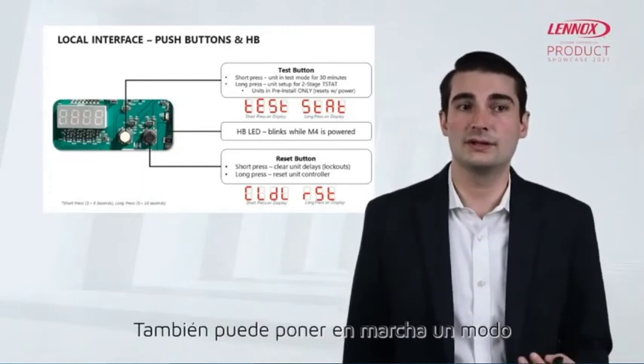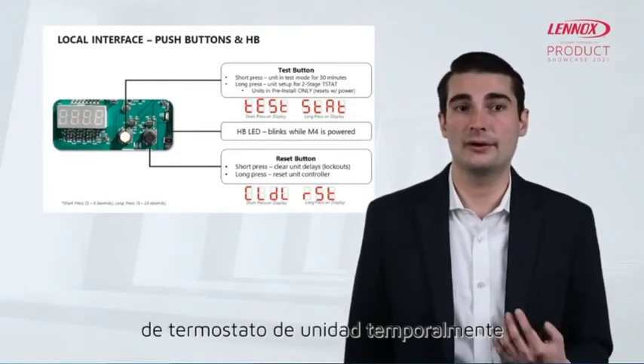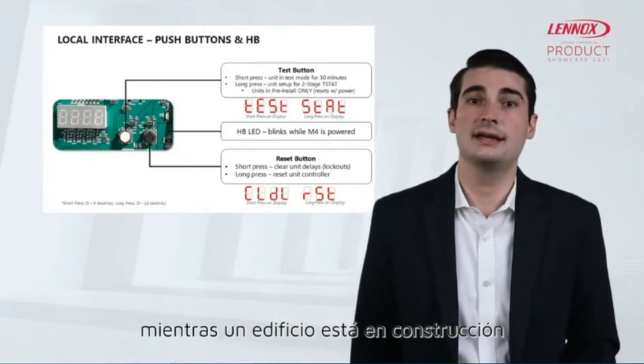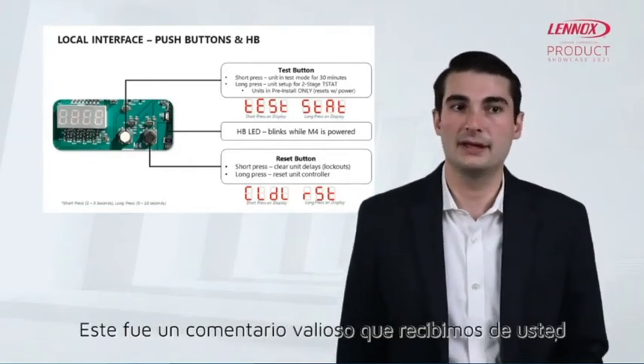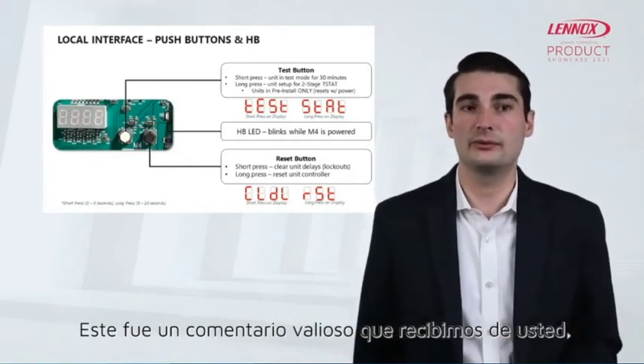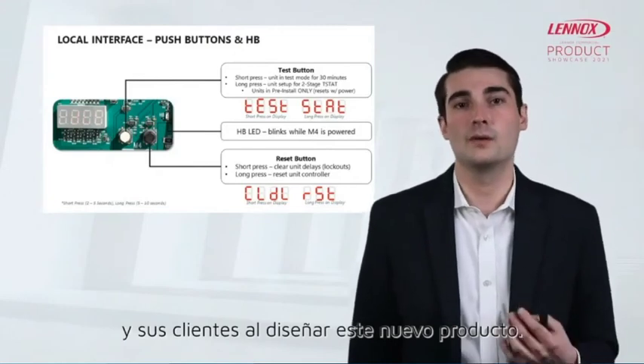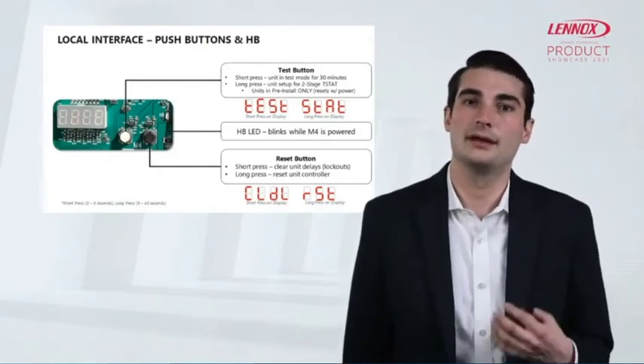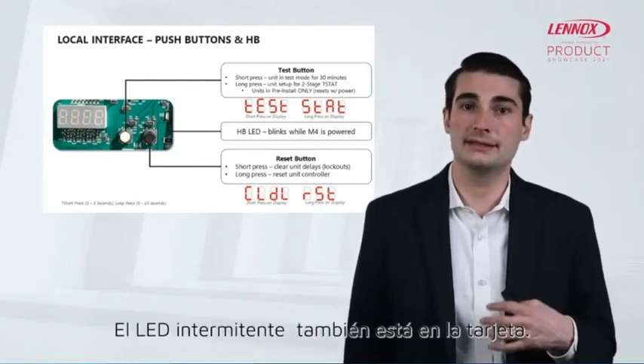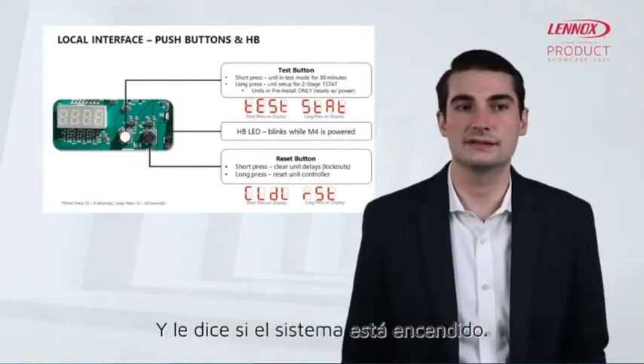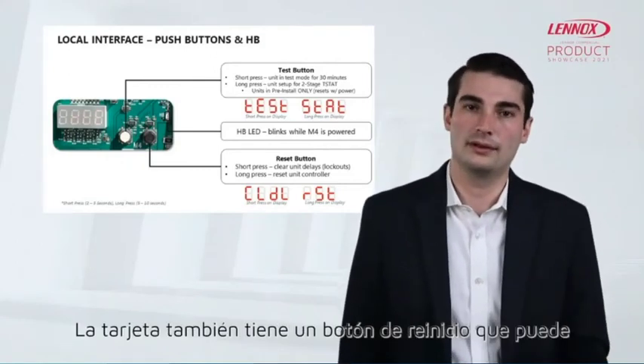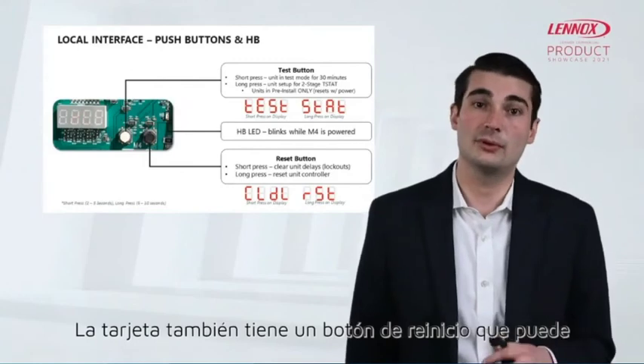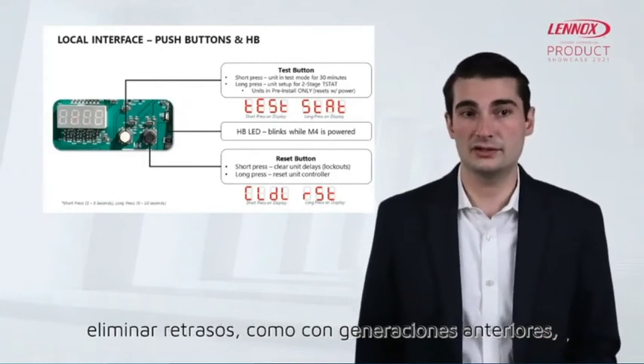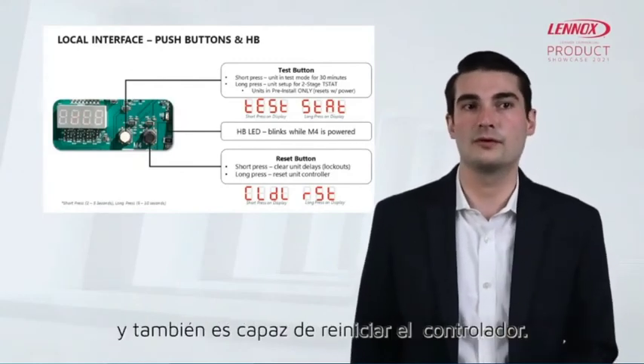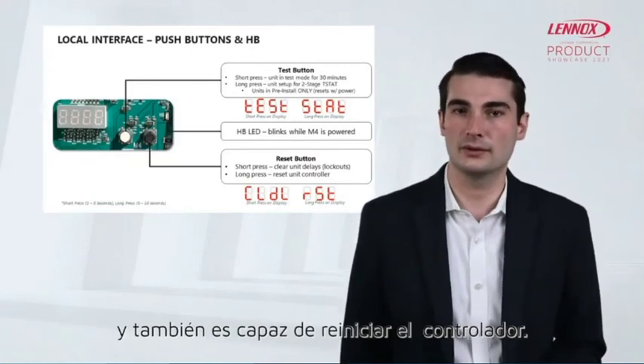It can also commission a unit to thermostat mode temporarily while a building is under construction if the final controls are not set up. This was a key piece of feedback that we received from you and your customers while designing this new product. The heartbeat LED is also on this board, and it tells you, of course, if the system is powered. The board also has a reset button that can both clear delays, as with prior generations of boards, and is capable of performing a reset on the controller as well.